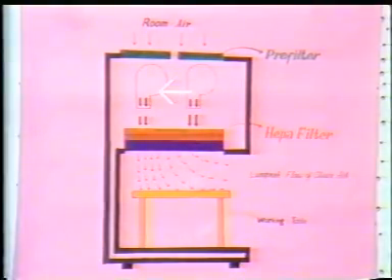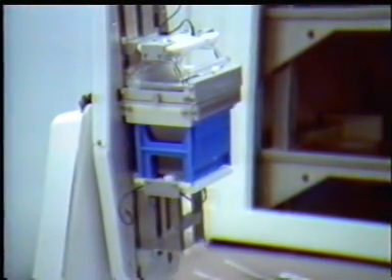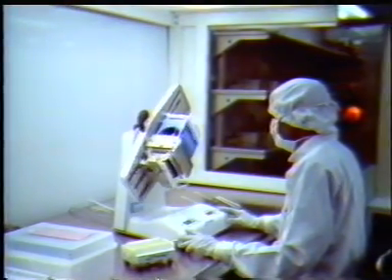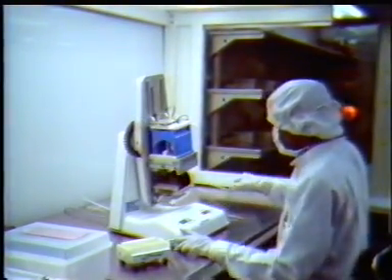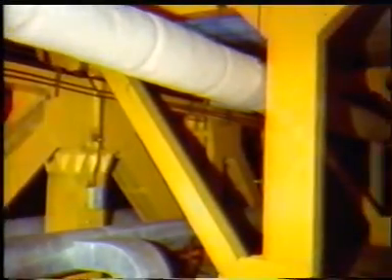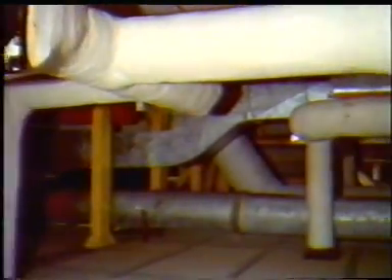However, the wafers are only exposed to air in a laminar flow unit. These units further purify the class 100 air of the room to class 10 condition. The wafers have to be processed by DI water, nitrogen, oxygen and other gases. Special pipelines with attached filters carry these in. Electrical connections, air conditioning ducts and all the pipelines are confined to the service corridors and mezzanine floor outside the actual working area to avoid dust and contamination.